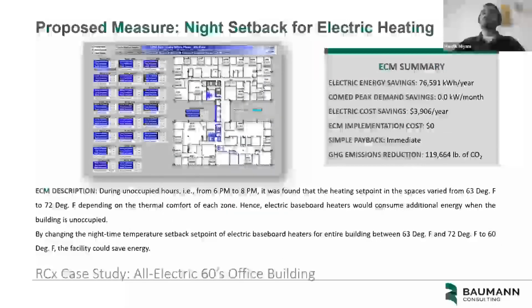Next ECM that we identified, looking into the set points: nighttime setback for the electric heating. During unoccupied mode, between 6 p.m. and 8 p.m., we found that the unoccupied set point for this particular building was set between 63 and 72. Due to which it was continuously consuming more and more energy for heating. So that is one place that we identified.